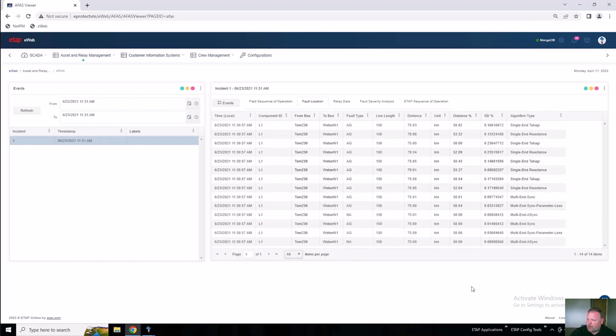Here, again, I'll show everything. Here we have multiple different ways of calculating the same fault location. So here we have the component name. This is line L1, the from bus, so one side of the fault on the faulted cable, and the to bus, which is the other side of the faulted cable. This allows us to understand what distance from what bus the fault is. If we can determine it, we get the fault type. So here it's an A to ground fault. The line length is extracted from the digital twin.